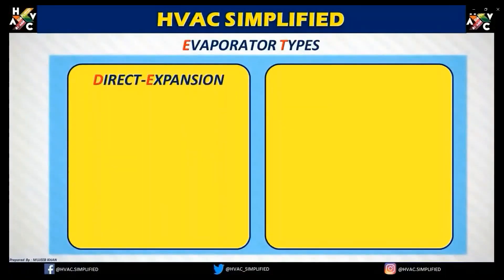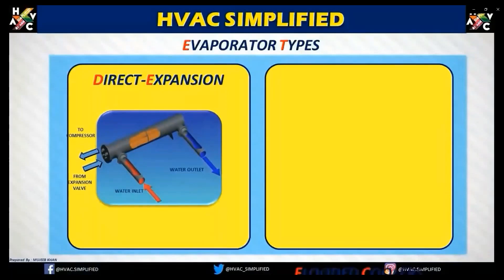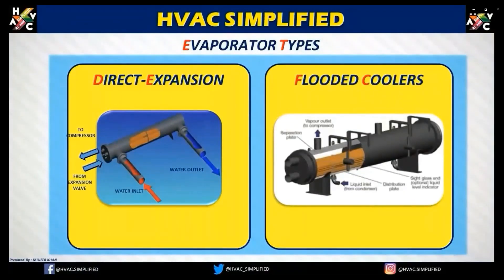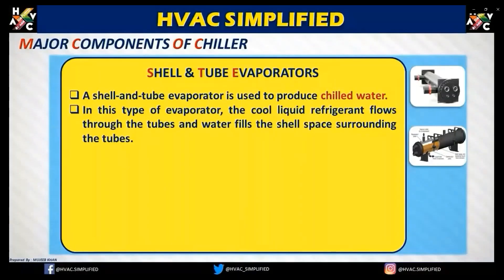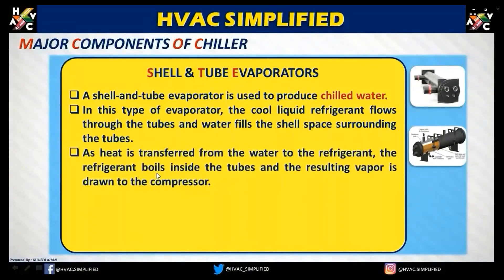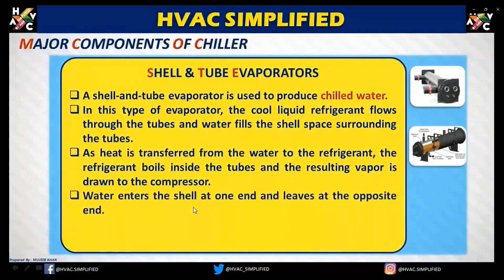Now let us see the evaporator types. The first is a direct expansion evaporator, and the second is a flooded cooler evaporator. In a direct expansion evaporator, a shell and tube evaporator is used to produce chilled water. The cooled liquid refrigerant flows through the tubes and water fills the space surrounding the tubes. Heat is transferred from the water to the refrigerant, and the refrigerant boils inside the tubes — the resulting vapor is drawn to the compressor.